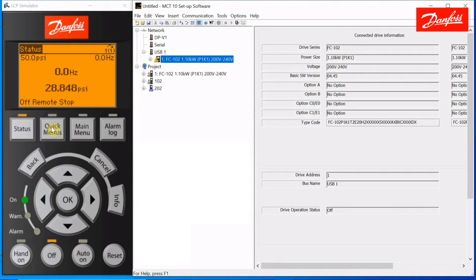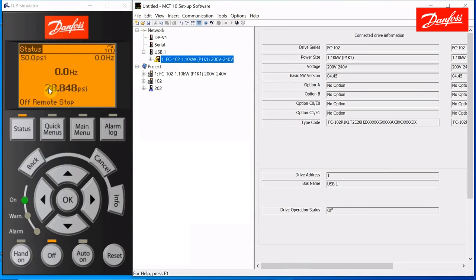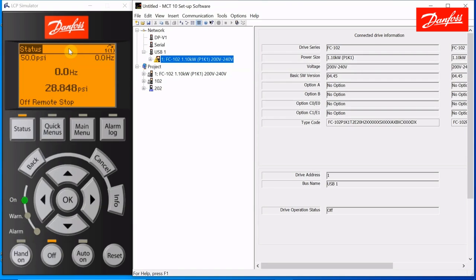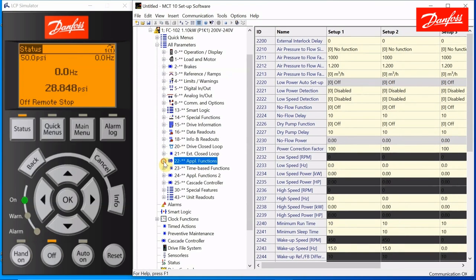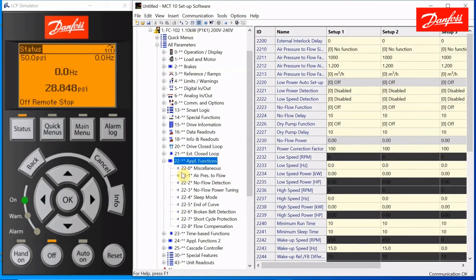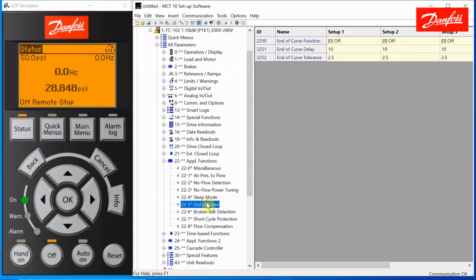Okay, let's see how this works. Here I have a drive. It's programmed in closed loop. It's got a simulated 0 to 100 psi pressure transmitter showing the feedback signal here. It's got a set point of 50 psi shown here. Both here and here we can see the speed that the drive is running. It's also configured so that when the relay activates, it'll show relay up here. The relay is programmed for end of curve. Here in the MCT10, let's look at the pertinent parameters.